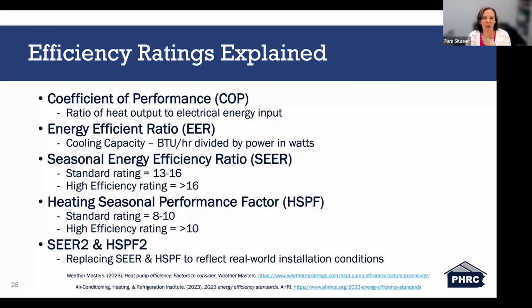So with that, the first one there is the coefficient of performance, or COP. This is the ratio of heat output to electrical energy input. A higher COP means better efficiency. For example, a heat pump with a COP of 4 provides 4 units of heat for every 1 unit of electricity consumed. And then moving on, we've got the energy efficiency ratio, the EER. The EER is primarily used for cooling performance. It's the system's cooling output in BTUs per hour divided by power consumption in watts. Again, the higher the EER, the more efficient the system is at cooling in a controlled environment.